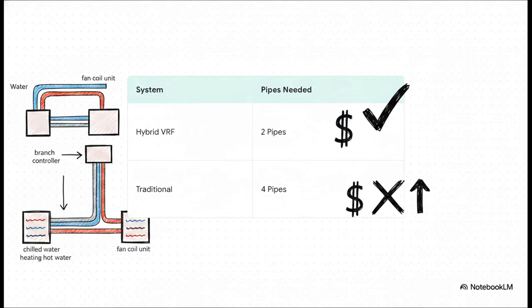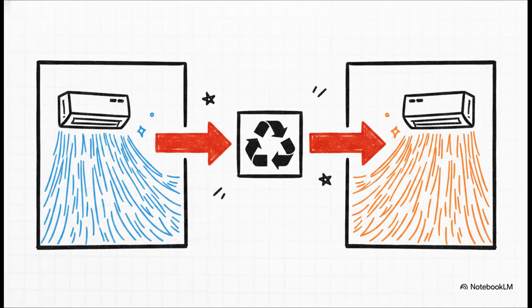That means double the piping, double the welding, and double the installation headaches. Going hybrid cuts down your installation complexity and your material costs massively compared to those bulky old 4-pipe setups. And by keeping those indoor spaces completely refrigerant-free, it's a huge win. You are instantly dodging major regulatory headaches and significantly lowering those rigorous leak detection requirements that come with running refrigerants through occupied areas. But wait, it gets even better.